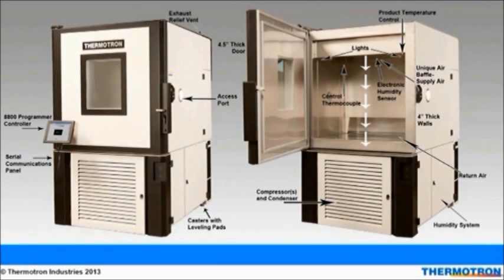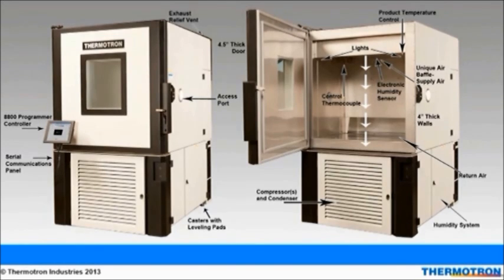Here is an example of how a typical chamber is laid out. First, we will go over the chamber on the left. Starting clockwise with the serial communications panel, you will find the control system right above it. Next, on the top right is where chamber pressures are released through the exhaust relief vent. Next, is an access port that allows wires and thermocouples to be placed on the product under test and hooked up to data acquisition equipment on the outside. Lastly, casters allow for easy chamber maneuvering.